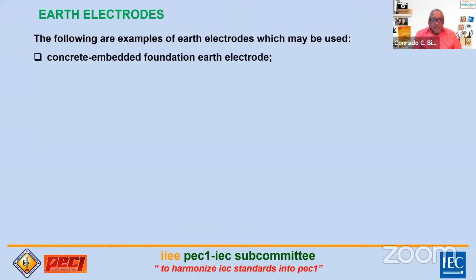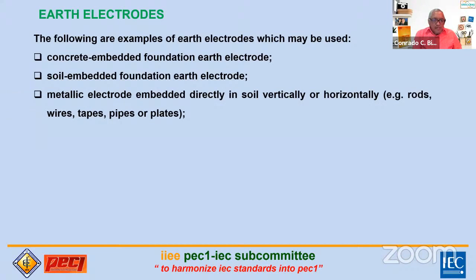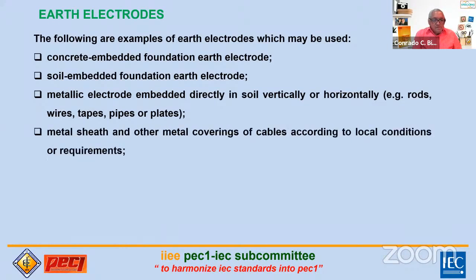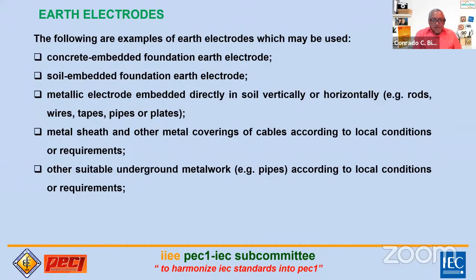So the following are examples of earth electrodes which may be used: concrete embedded foundation earth electrode, soil embedded foundation earth electrode, metallic electrodes embedded directly in soil vertically or horizontally such as rods, wires, tapes, pipes, or plates, metal sheath and other metal coverings of cables according to local conditions, and other suitable underground metal works or pipes according to local requirements.